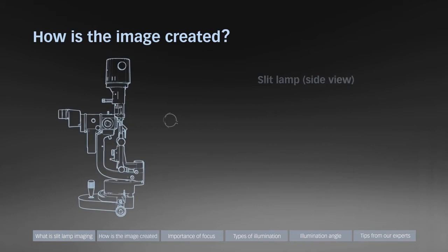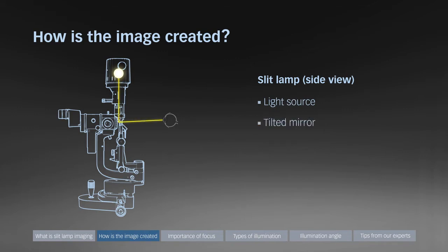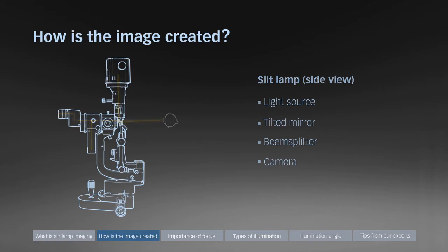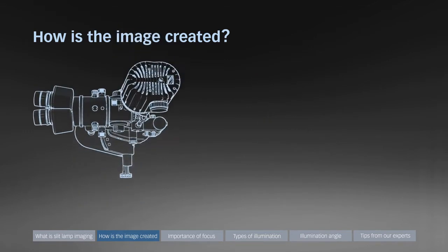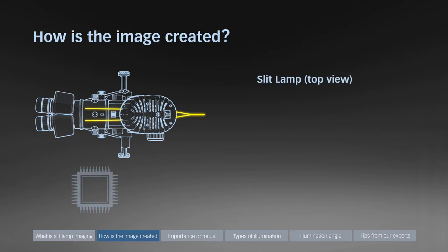How is the slit lamp image created? It all starts in the illumination head of the slit lamp. The light passes the optics, is diverted by the mirror and illuminates the patient's eye. From there it passes the optics, is divided by the beam splitter and reaches the camera sensor and the examiner's eyes. The camera captures the image of only one light path. Always keep in mind on which side your camera captures the images.